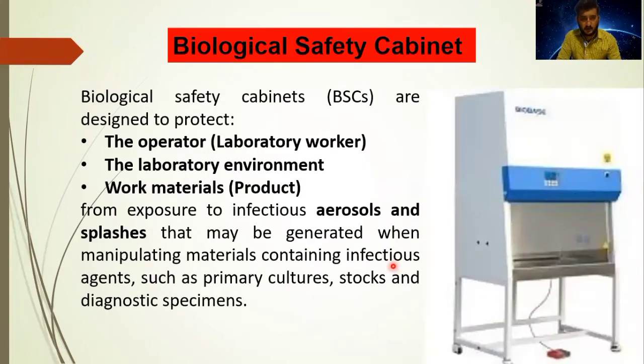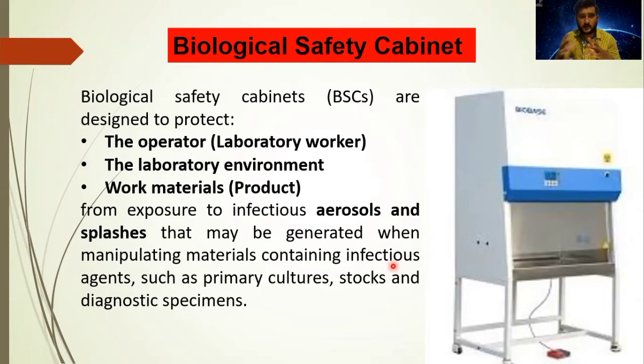First of all we will see the definition of biological safety cabinet. Biological safety cabinets are designed to protect the operator, the laboratory worker, the laboratory environment, and the working material or product from exposure to infectious aerosols and splashes that may be generated when manipulating materials containing infectious agents such as primary cultures, stocks, and diagnostic specimens.